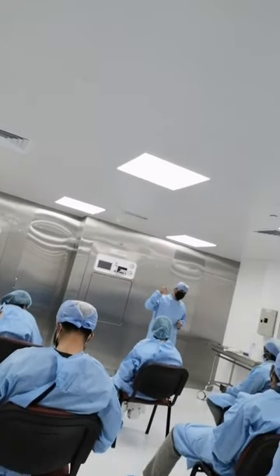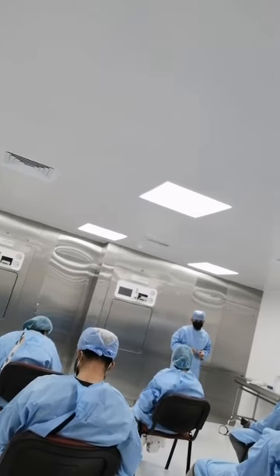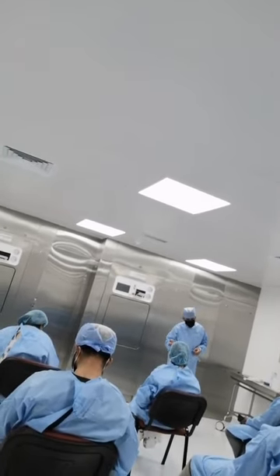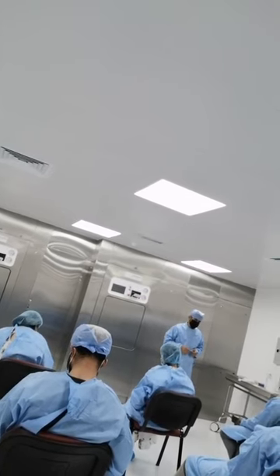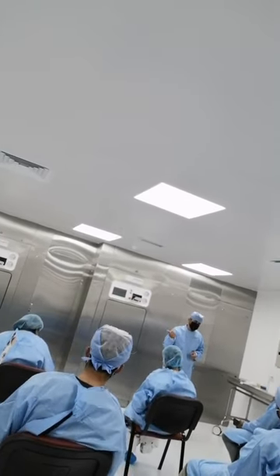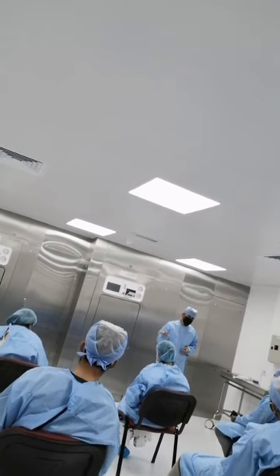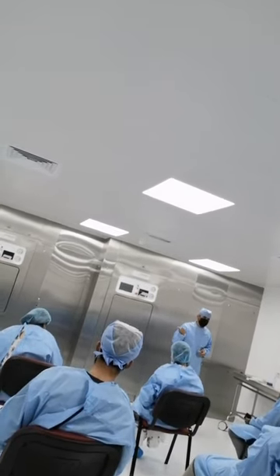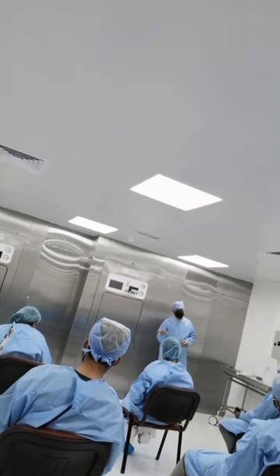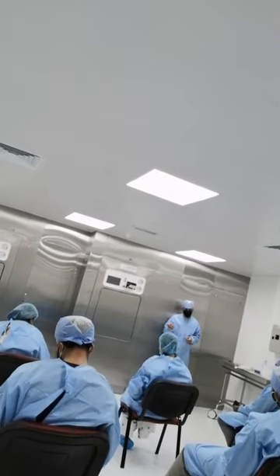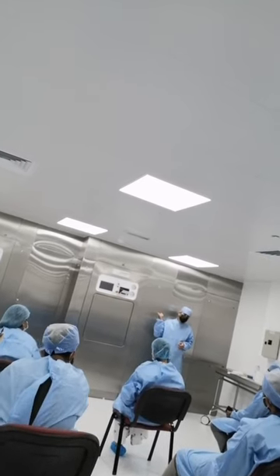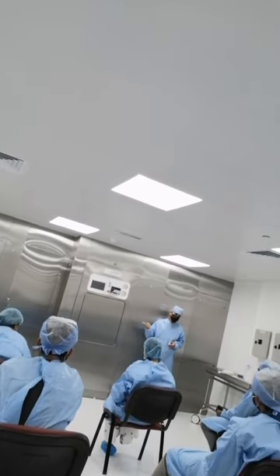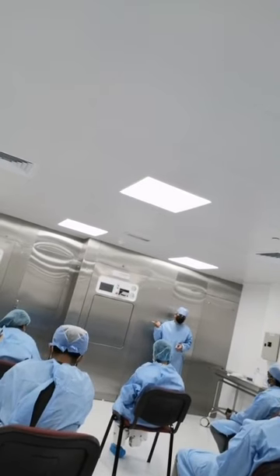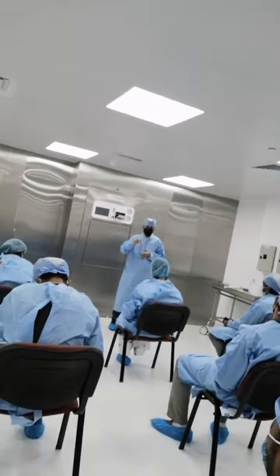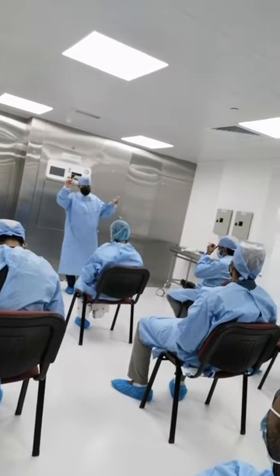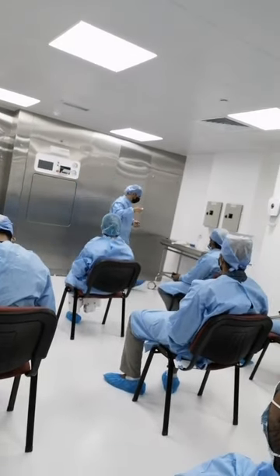Okay? The more the class, the more accurate is the result. Okay? 74% is the accuracy of the +4, 85% is the accuracy of +5. 94% is the accuracy of +6. Accuracy of what? Time and temperature of the sterilization phase. Again, 74, 85, 94. These are the accuracy of the indicators +4, +5, +6. Of type 4, type 5, type 6.